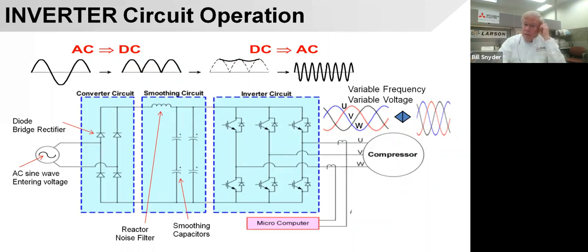And if you really want to calculate it, you take your input here and multiply by the square root of 2, and the square root of 2 is 1.414 and a bunch of digits behind it. If you take 1.414 times whatever that electricity is coming in here, it'll pretty much give you what your DC voltage is coming out. So if you've got 212 volts going in, you will have 300 volts coming out. If you got 208, you've got 294. If you're at 230, we'll be at 325. To give you an idea, we always refer to this as around 300 volts. It's not going to be exactly 300 volts, but a lot of the slides we show you 300. The only time it's going to be 300 volts is if you got 212 volts steady coming in.